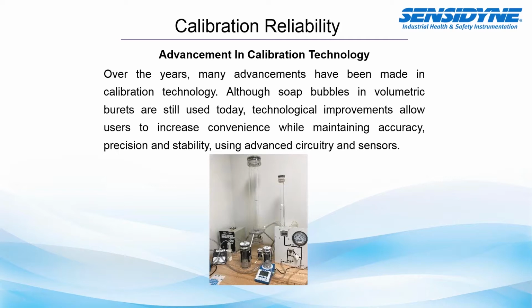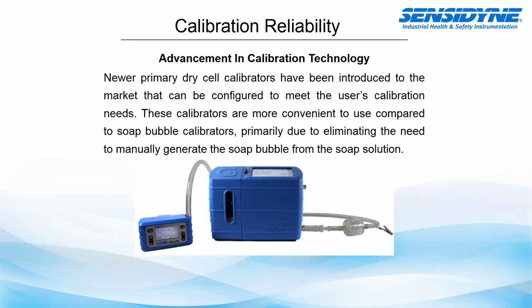Now let's talk about some advancements in calibration technology. Over the years, many advancements have taken place. Although soap bubbles are still used in volumetric burettes today, technological improvements allow users to increase convenience while still maintaining that high accuracy, precision, and stability, using advanced circuitry and sensors which have been integrated into today's instrumentation. Newer primary dry cell calibrators, which were introduced to the market, can be configured to meet users' calibration needs. These calibrators are more convenient to use compared with the older soap bubble calibrators, which are also primary, primarily due to eliminating the need to manually generate the soap bubble from the soap solution.